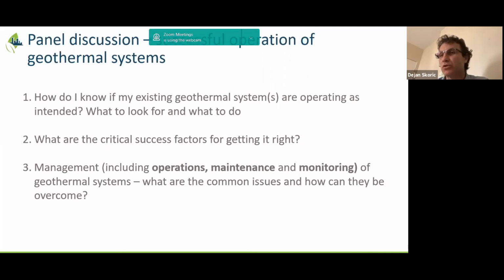During the design, we should set the intent so operators know what temperatures are supposed to happen each season over a typical 20-year period. There are now even third-party predictive algorithms, web-based systems being developed that you can tap into and pay for, but the principle is the same: if we know what the loop temperatures are supposed to be as part of the design, then if something goes higher or lower than expected, we need mitigating steps and need to tell operators what to do. Jeff mentioned heat sinks, snow melt, or a fluid cooler as a last resort, putting heat into the air, and the same on the cooling side.